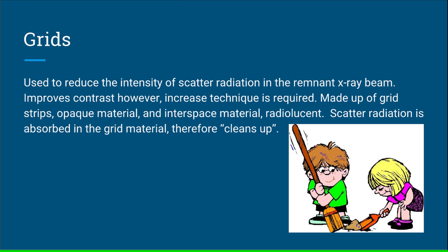Grids are used to reduce the intensity of scatter radiation in the remnant x-ray beam. They improve contrast; however, increased technique is required. Grids are made up of strips of opaque material and interspace material, which is radiolucent. Scattered radiation is absorbed in the grid material, therefore it cleans the image up.